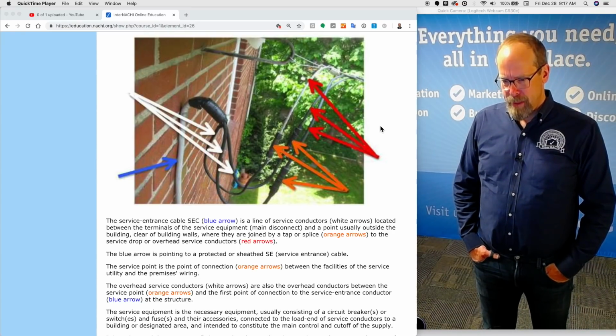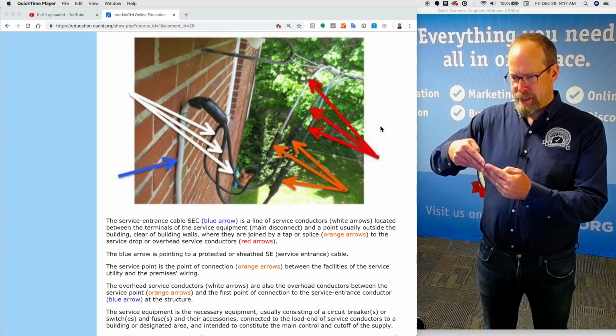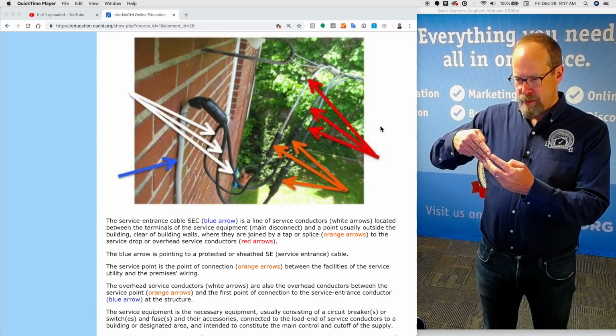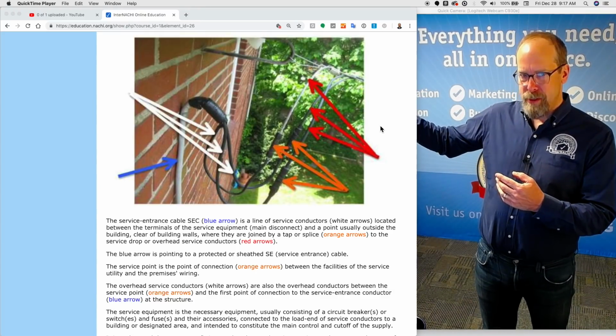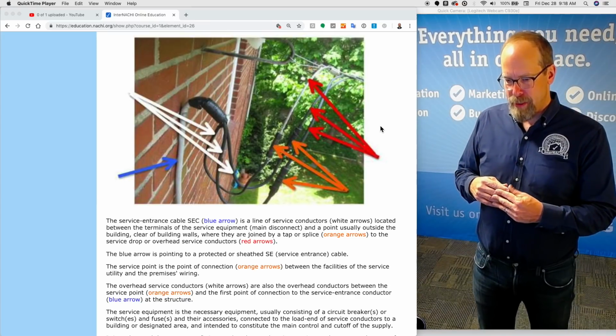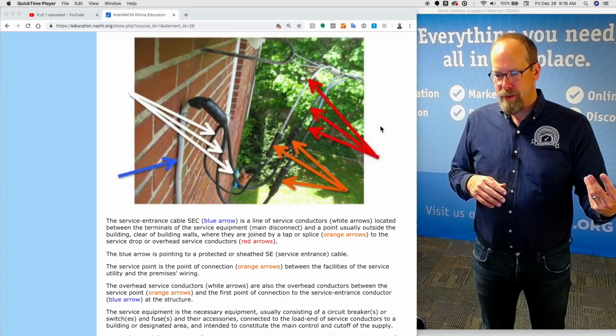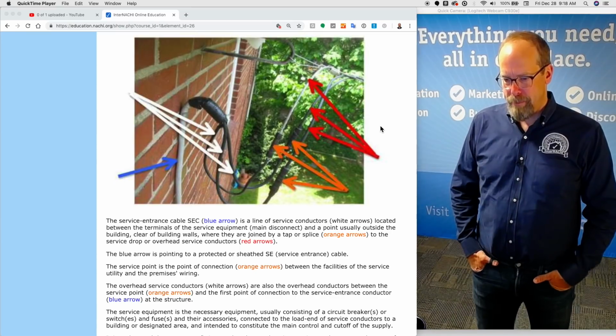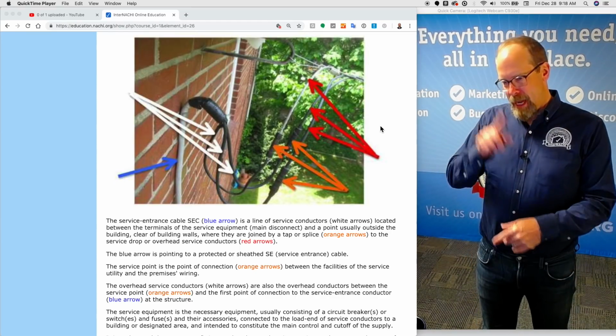The service point is the point of connection. That's that splice. That's the orange arrows there. Between the facilities of the service utility, the utility coming in, the service coming in, and the house wiring. So that's the service point. And that's at the drip loop too.